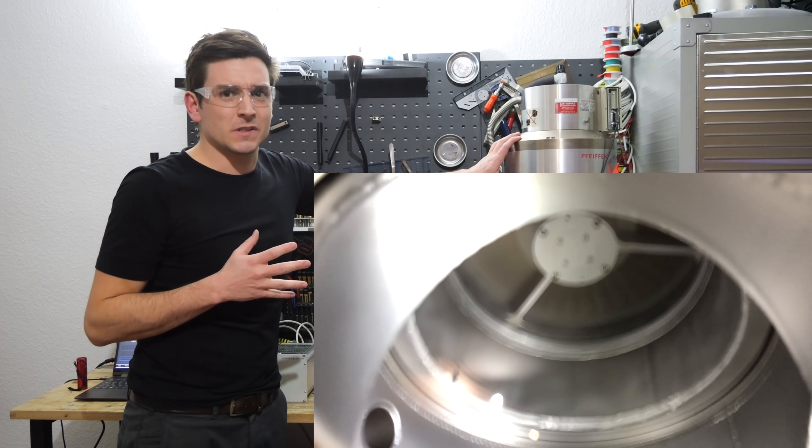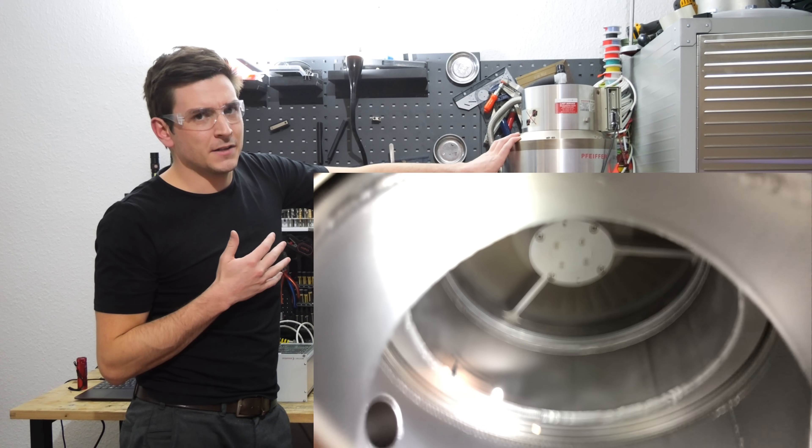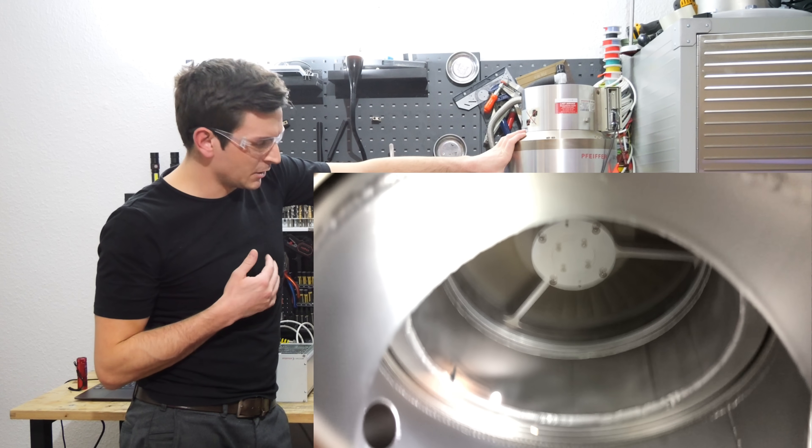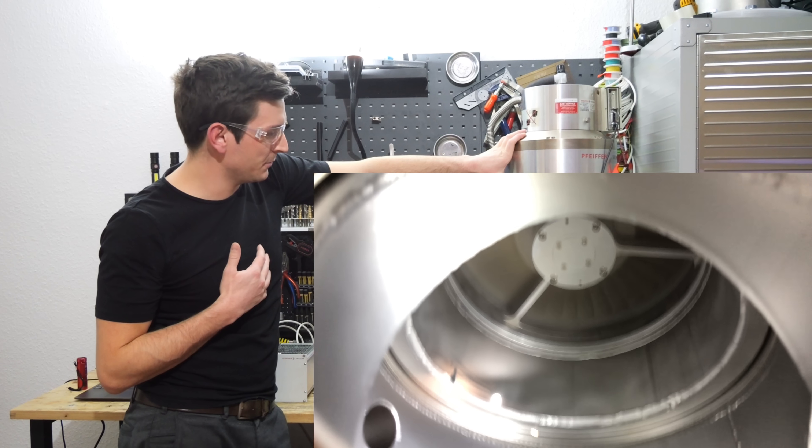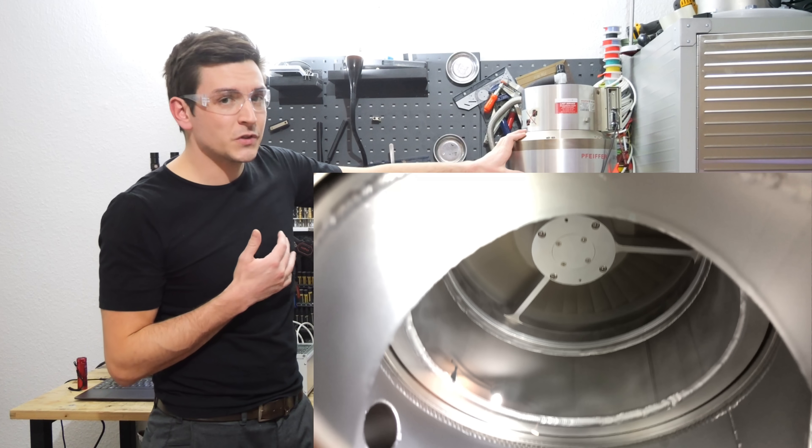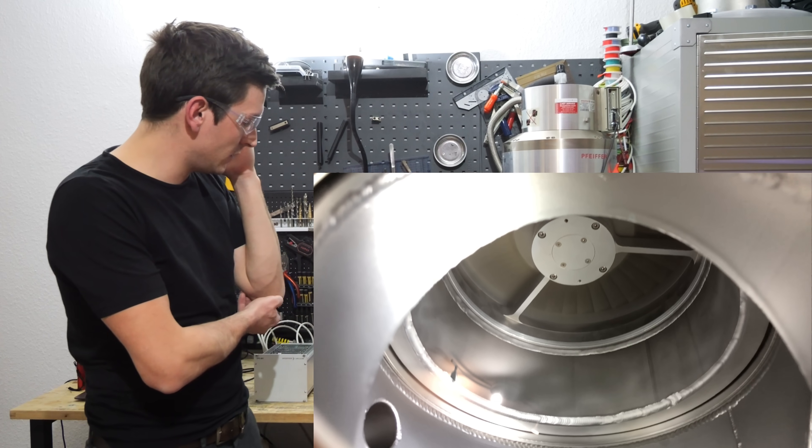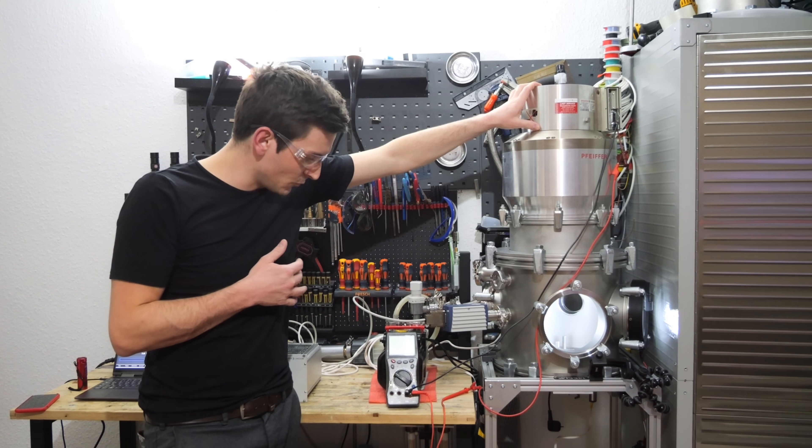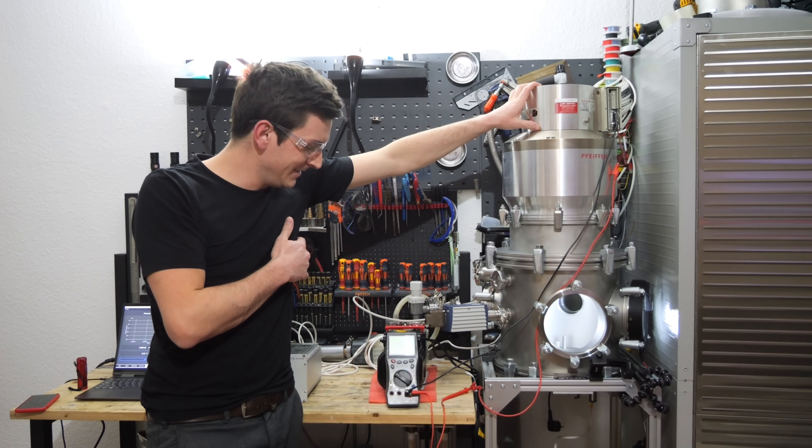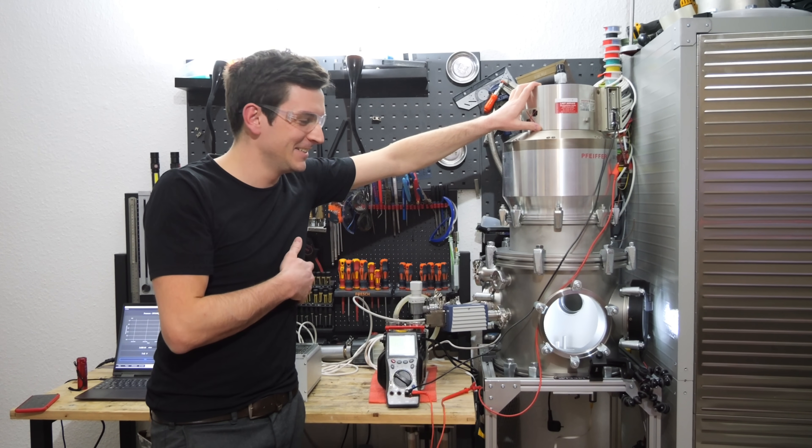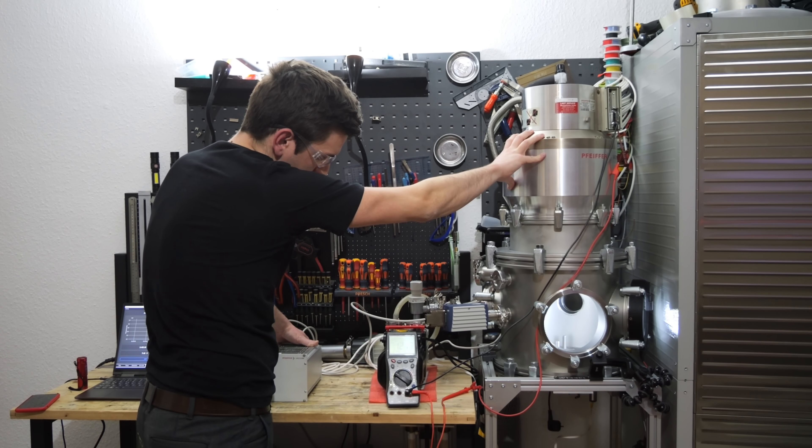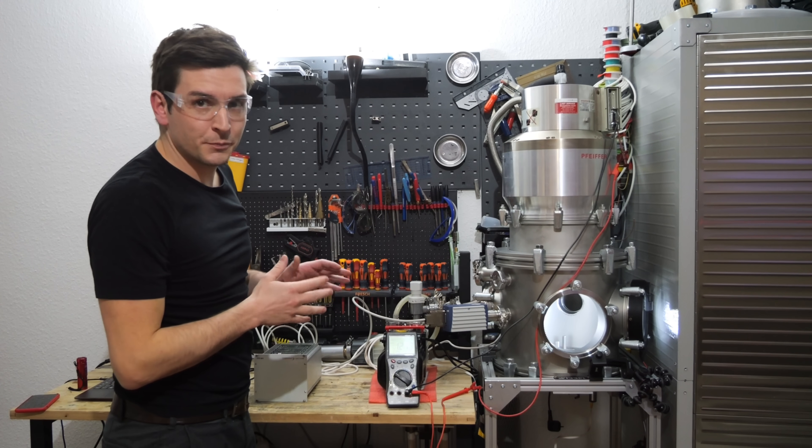And we do hear the same noises. And you can feel quite the vibration coming from the pump. In my opinion it shouldn't sound that way. Interestingly, it happens at 10 percent of the speed. I'm wondering if it's an area of resonance for this pump. So maybe if we exceed this range it will stop.